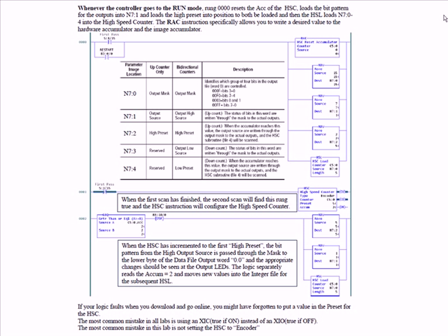The electronic counter can increment based on the rise and fall rate of the electronics itself, which we mentioned was 6600 Hertz, meaning it's a physical limitation. It is not limited by the scan rate, meaning that a count up or count down instruction that is instructing C50, C51, C52, any of the counter predefined data types, can only increment or decrement the data file after each input image scan.